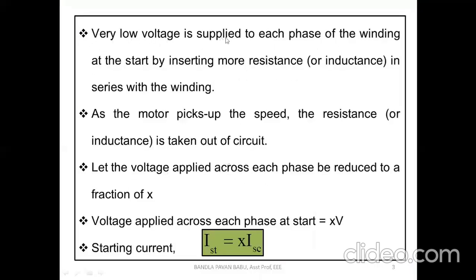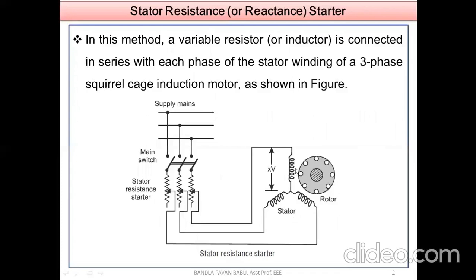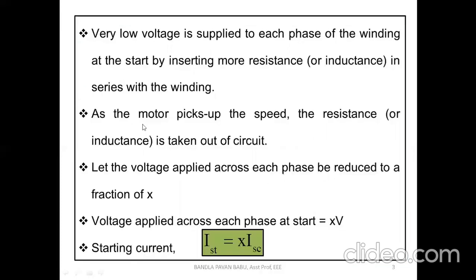Next, very low voltage is applied to each phase of the winding at the start by inserting more resistance or inductance in series with the winding. So that's what I mean. Especially when we are conducting the laboratory test regarding the magnetization characteristics, likewise at the generator side, we are going to apply the maximum resistance, so that gradually we are going to apply the rated voltage. We are making it to excite the voltage, so we are going to control that. So likewise here also, we are applying a very low voltage at the stator side.